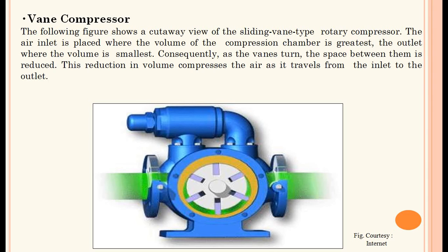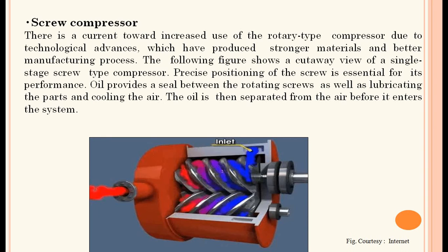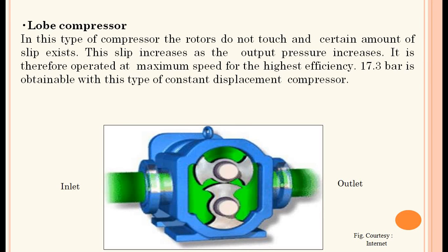A vane compressor is shown — it is a sliding vane type rotary compressor. The air inlet is placed where the volume of the compressor chamber is largest and the outlet where the volume is smallest. As the vanes turn, the space between them is reduced, compressing the air as it travels from inlet to outlet. Then the screw compressor and lobe type compressor are also covered.